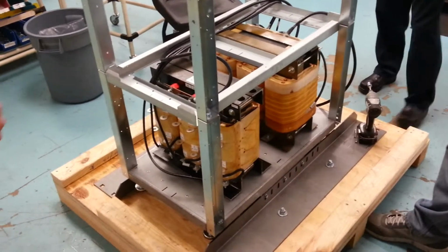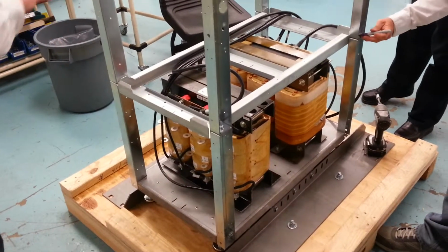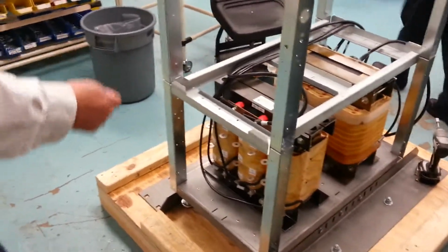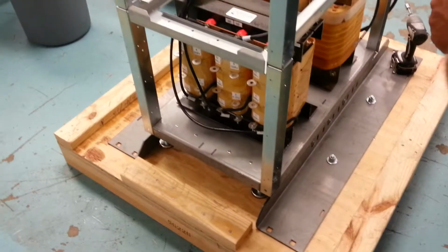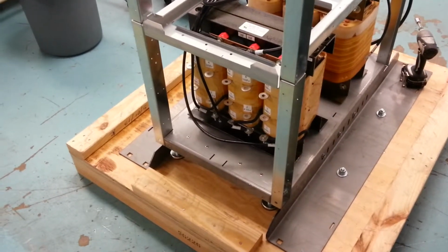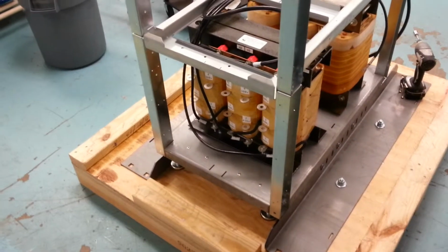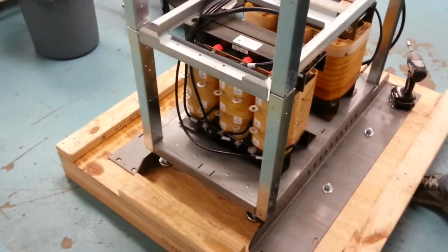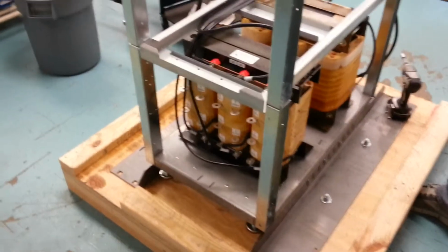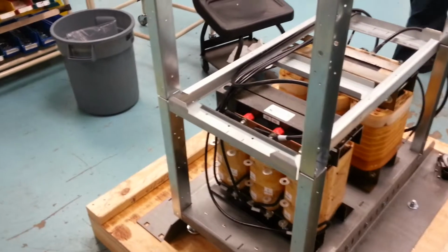If they want a special unit, we can put special transformers in there, change the taps, see how they're all listed, 480 to 208 tappable. We just change the actual delta reference or the Y reference, and we can change the voltage coming in and out of the unit and not interfere with the 208 nominal voltage and current that's inside the unit.